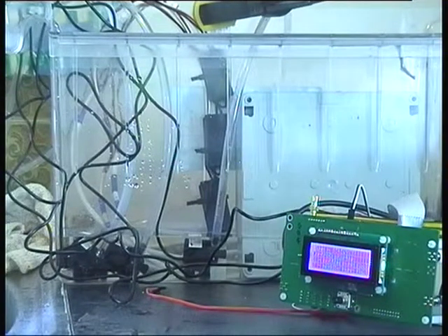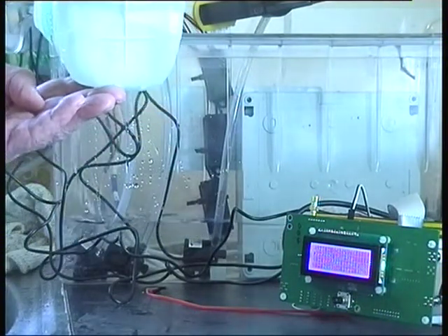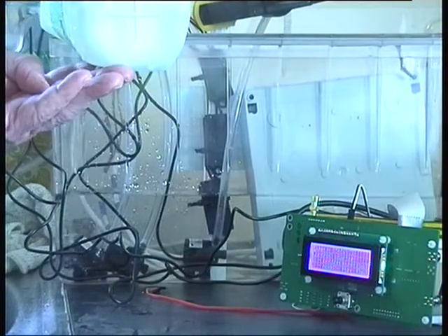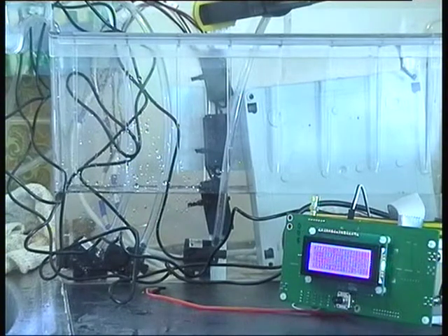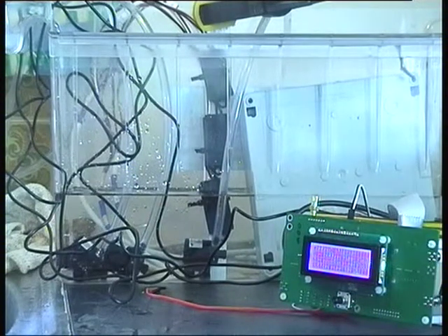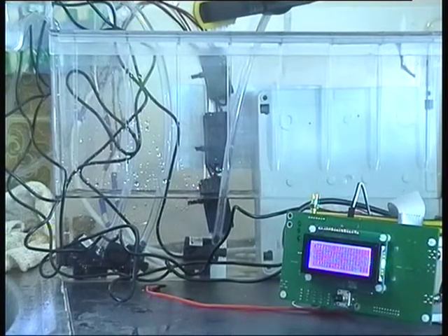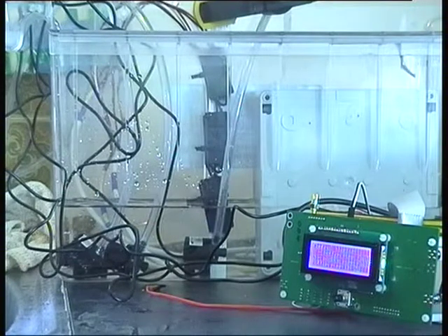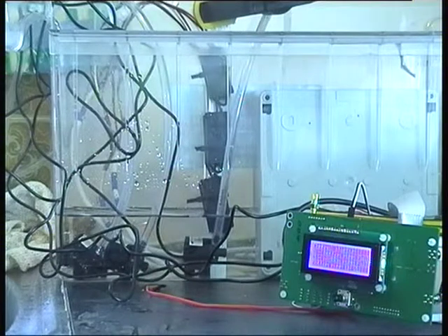We will now show normal operation of the system. The bottom sensor is activated and switches on the associated pump, which should now lower the level to a normal operating level.